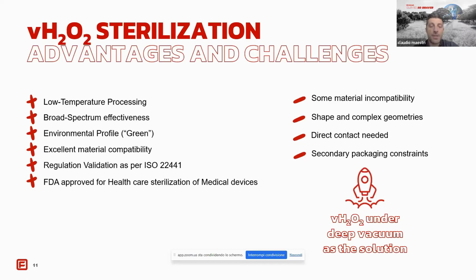So, despite its advantages, H2O2 also presents specific challenges that require careful consideration in process development. So, for sure, the first one is some material incompatibility. The primary challenge of H2O2 is its incompatibility with cellulosic materials. Cellulose degrades hydrogen peroxide, compromising sterilization effectiveness. Additionally, certain uncoated reactive metals, such as copper and brass, may react with H2O2, leading to surface degradation or discoloration. These issues need careful material selection for devices and critically for primary packaging. Second one: shape and complex geometries, direct contact needed, and some secondary packaging constraints.